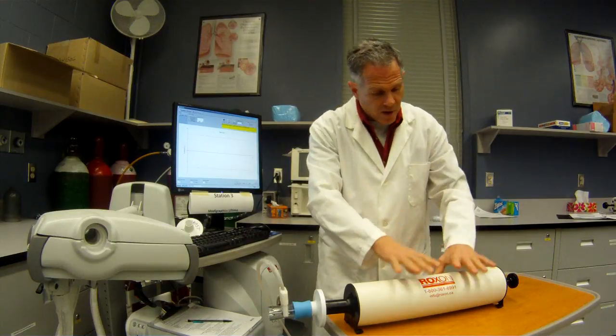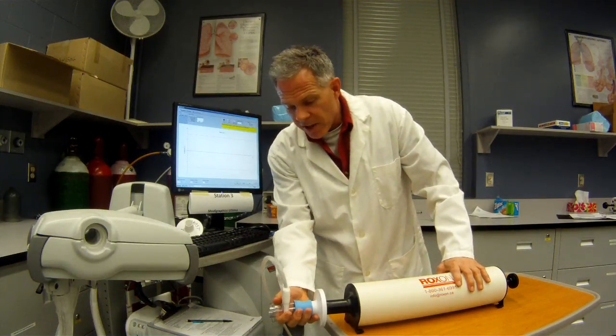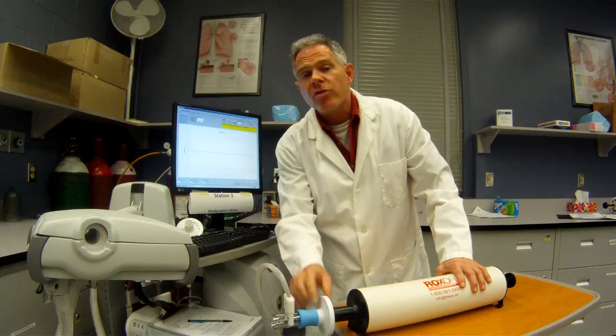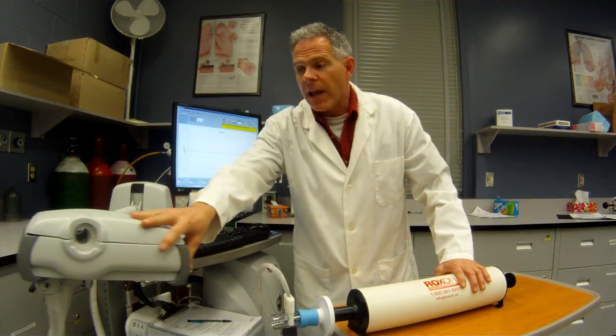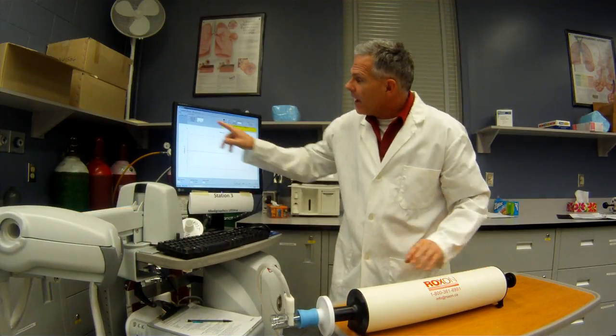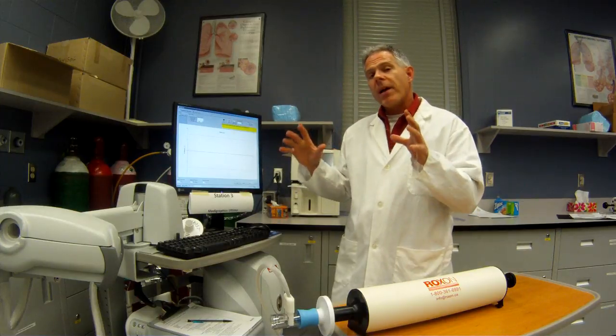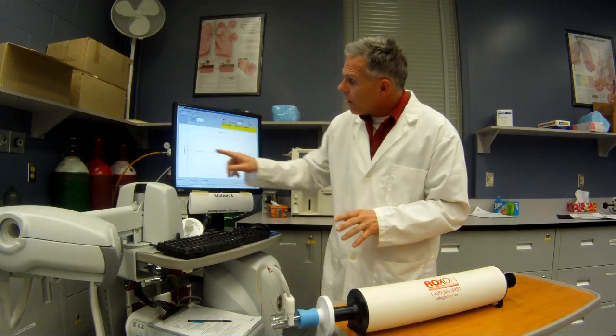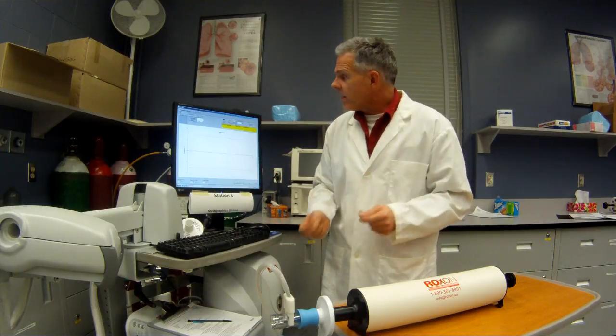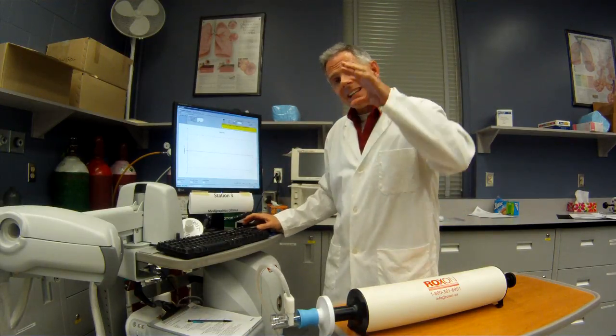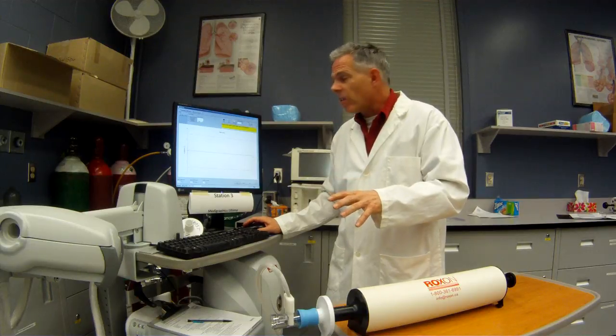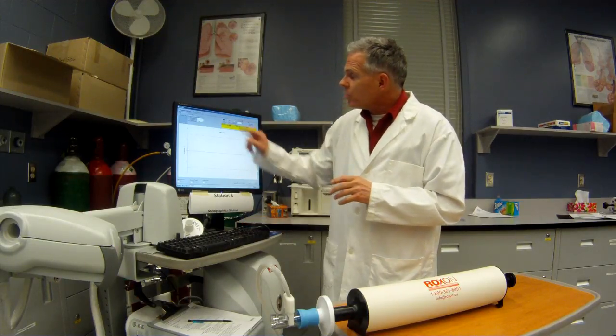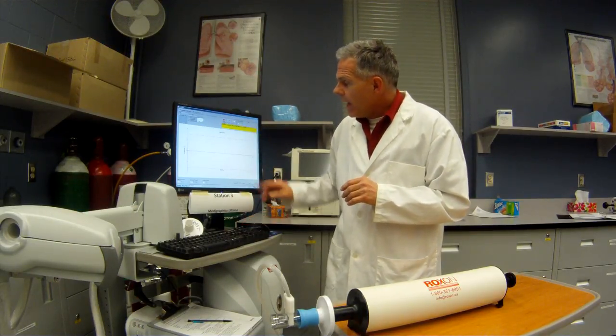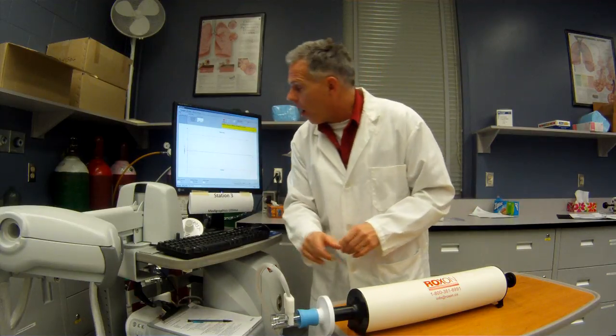Okay? So I've got my 3-liter syringe. I've got my pneumotach hooked up to the end. And I've got a filter here just mimicking what we would have with our patient on here. Now, on this little screen here, it captures some elements that are important for a calibration. We have to do it at a wide variety of flow rates. With this particular device, it actually does the calibration and verification at the same time. So we'll just hit start, okay? And it tells me to withdraw 3 liters.